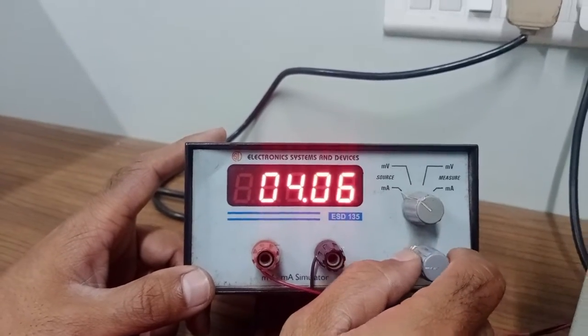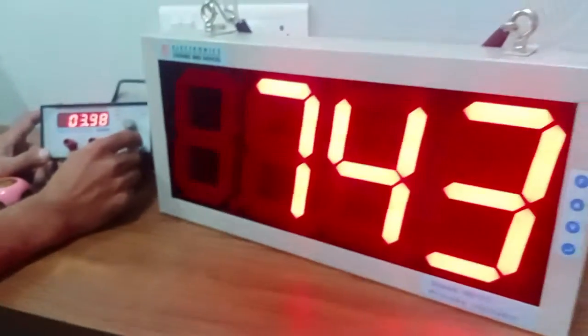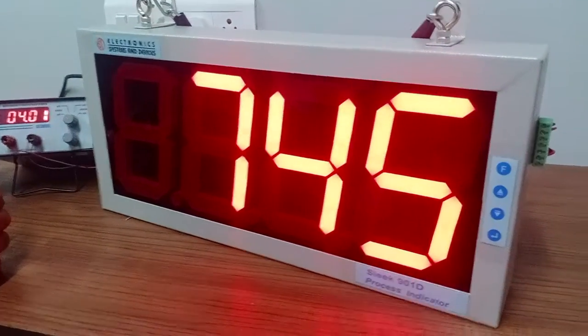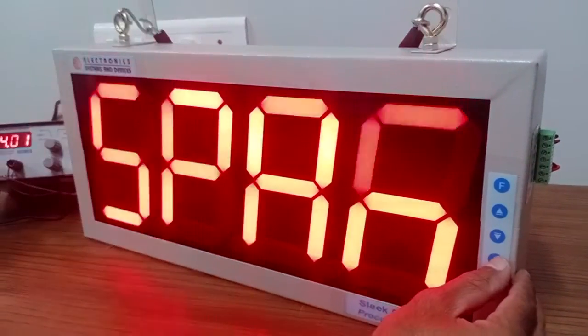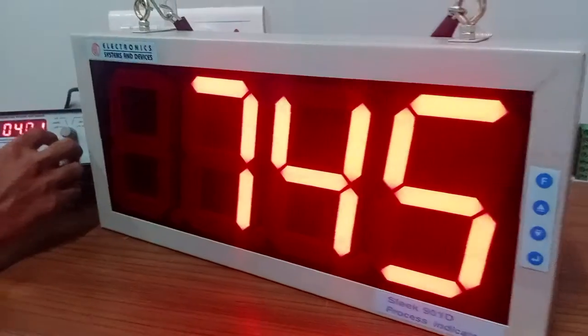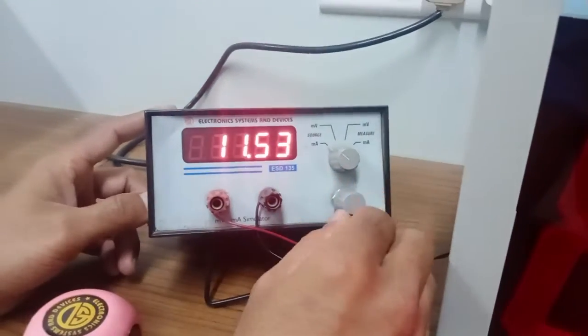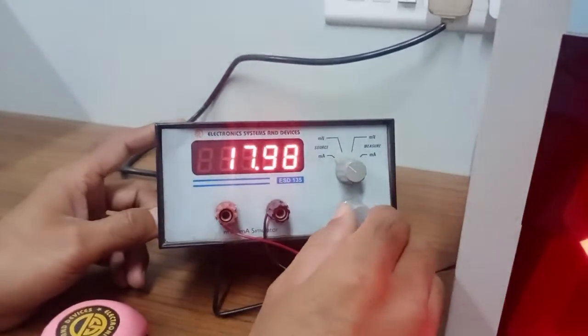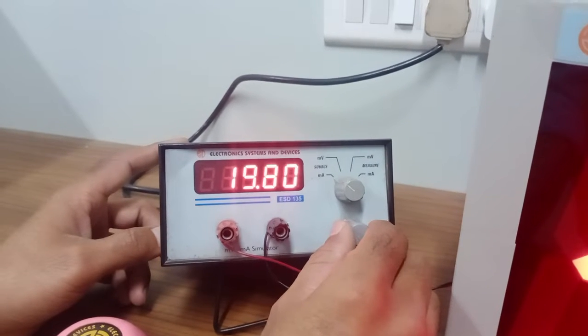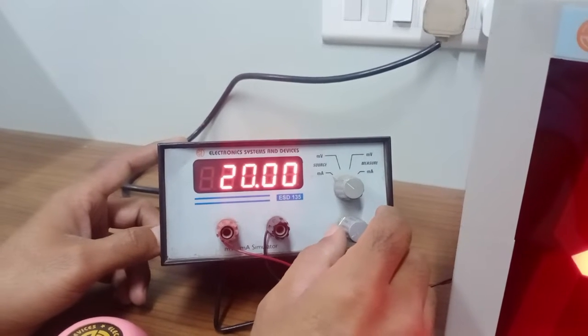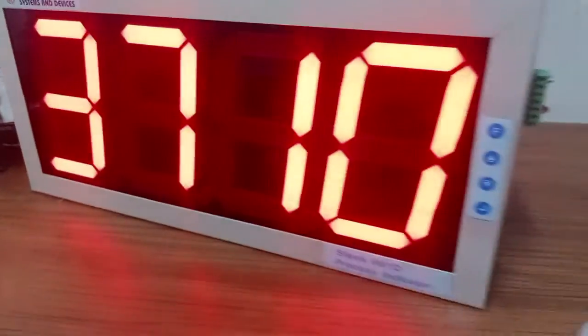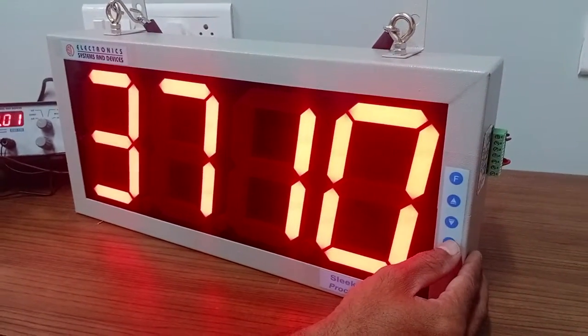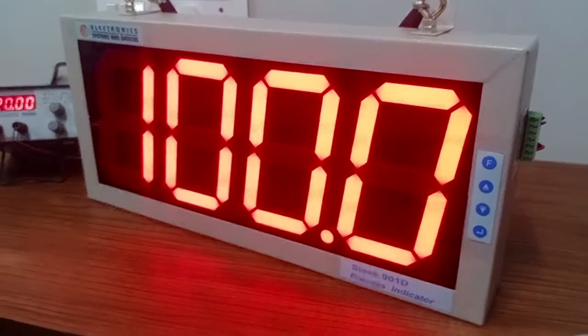In the calibration mode, 4.00, we press enter. We will go to the next, that is the span reading. Then we will feed the 20 milliampere reading, 20.00. OK, we will press enter. This completes the calibration.